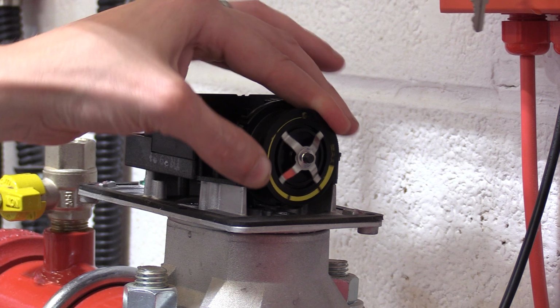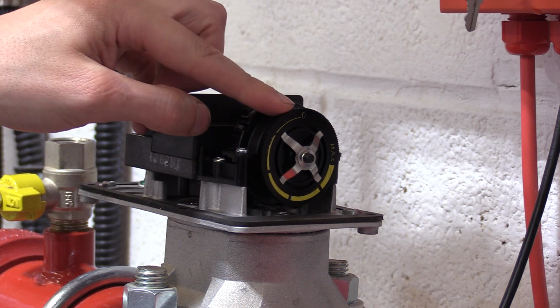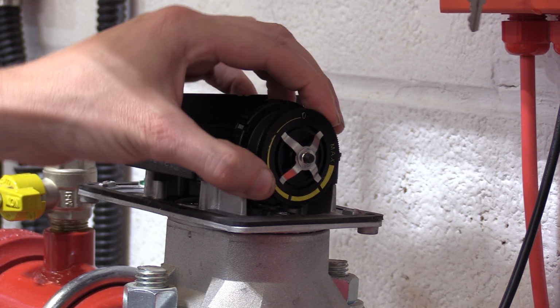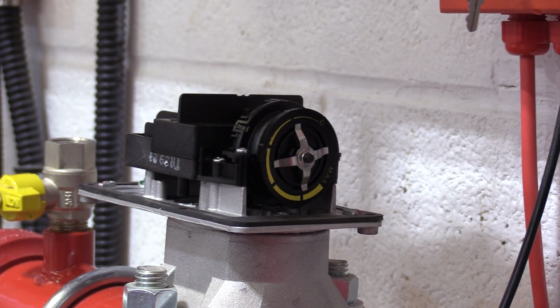Check the delay timer settings. Turn the dial to minimum settings while conducting troubleshooting. This should be returned to the desired delay once troubleshooting is completed. We recommend between 5 and 10 seconds.